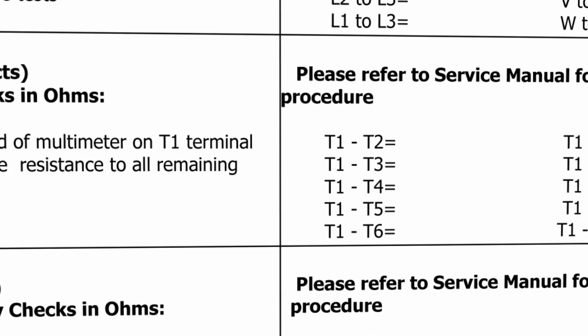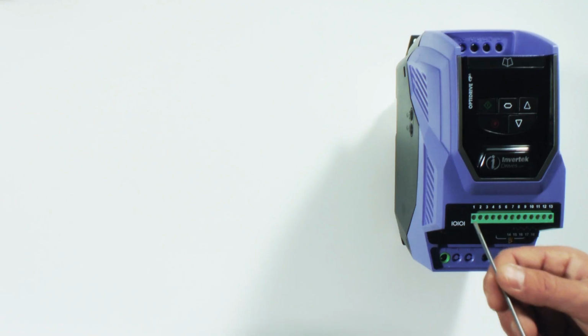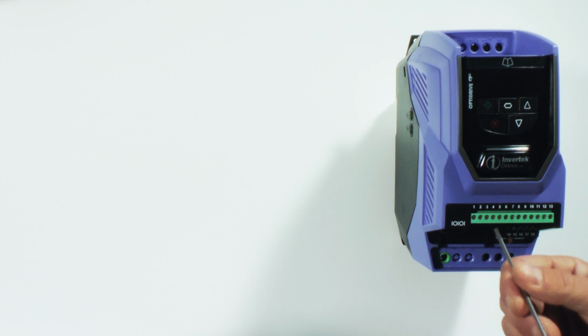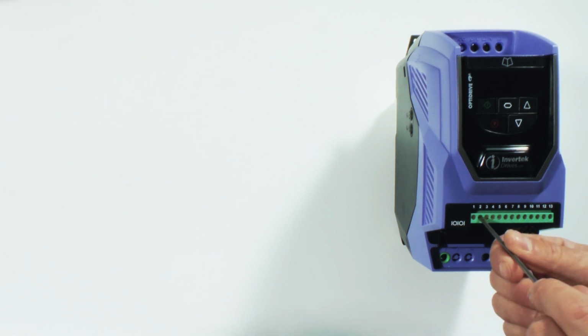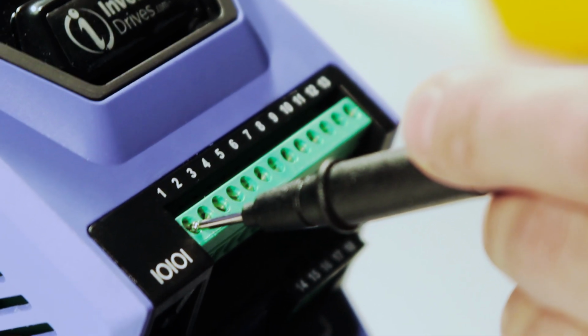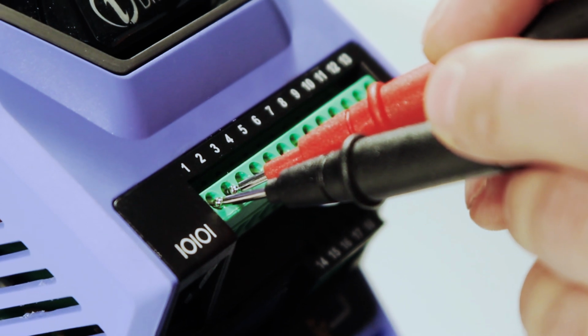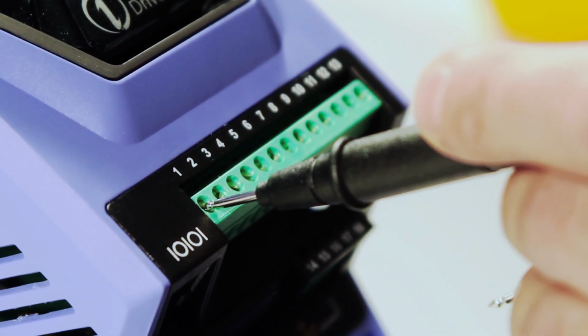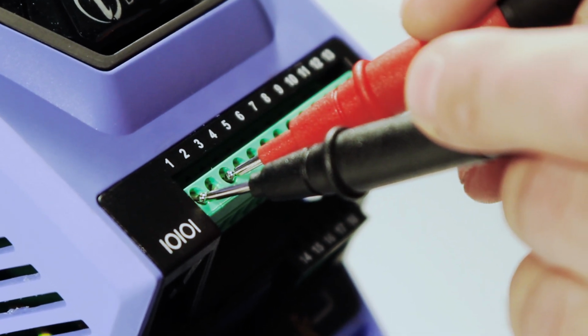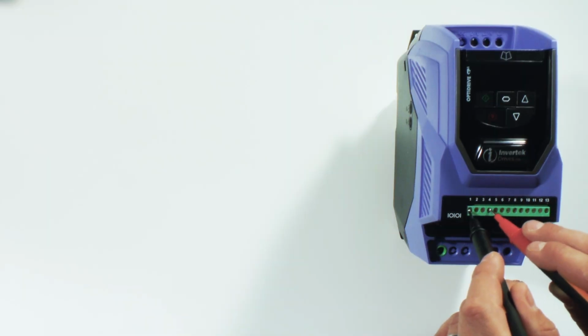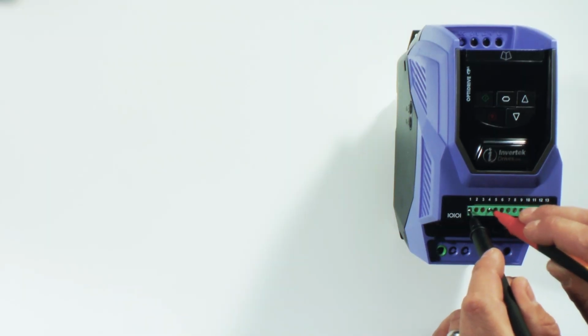Control terminal checks. Ensure terminal blocks are screwed down using the terminal screwdriver. Place the black multimeter lead on terminal 1, then the red multimeter lead on the remaining control board terminals. Complete the service request form with your readings.